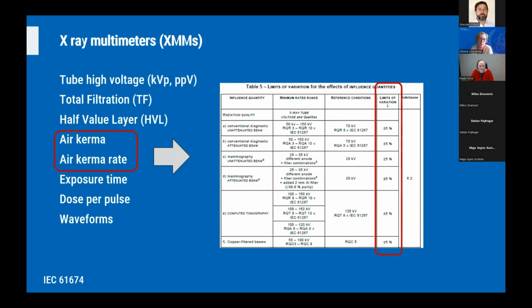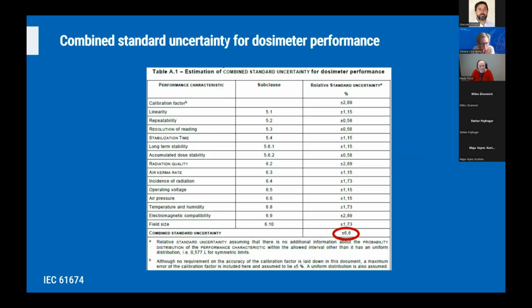Properties of X-ray multimeters as dosimeters are defined by the IEC standard 61674. If you look at Table 5 of this standard, you will see that for the range of standard radiation qualities, the uncertainty of these dosimeters should be within 5%, which is the case for almost all multimeters, as presented earlier by Stefan.